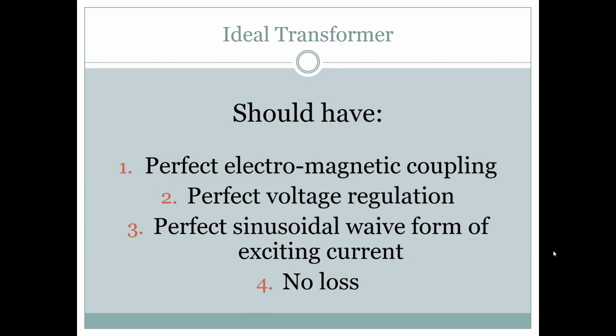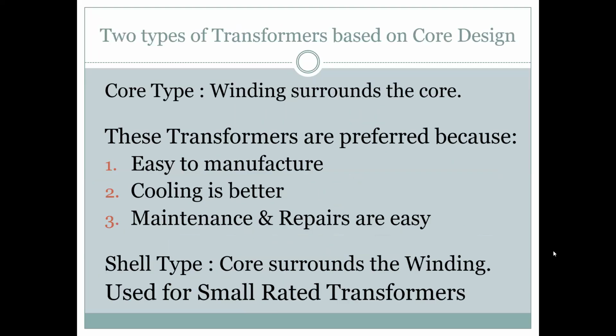But unfortunately, our system voltage is so fluctuating that all these specifications have changed to 10% voltage variation, 5% frequency variation, and 10% combined variation. Now we are not able to feed quality power to the product, and we are making the product the most difficult one to design. That is the scenario as of today. So I have to take care of all this during my design: a perfect sinusoidal waveform during excitation, and no loss. The more I can reduce the loss, the more the transformer efficiency will go up. For that we need good steel, and better conductors and coils, a new generation, so you can reduce the loss. But we are concentrating on that.